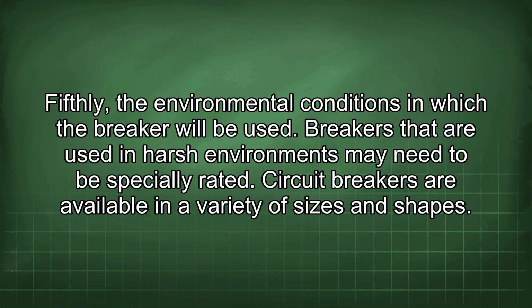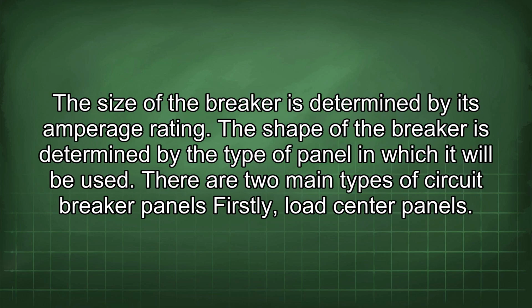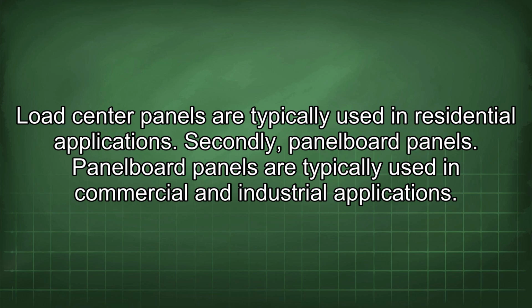Circuit breakers are available in a variety of sizes and shapes. The size of the breaker is determined by its amperage rating. The shape of the breaker is determined by the type of panel in which it will be used. There are two main types of circuit breaker panels. Firstly, load center panels. Load center panels are typically used in residential applications. Secondly, panel board panels. Panel board panels are typically used in commercial and industrial applications.